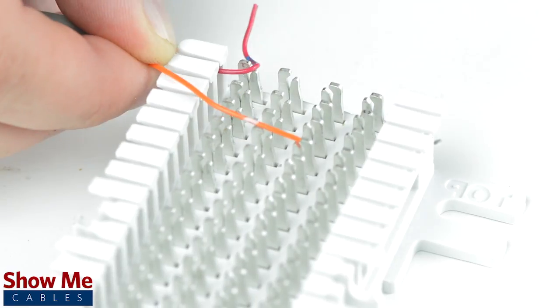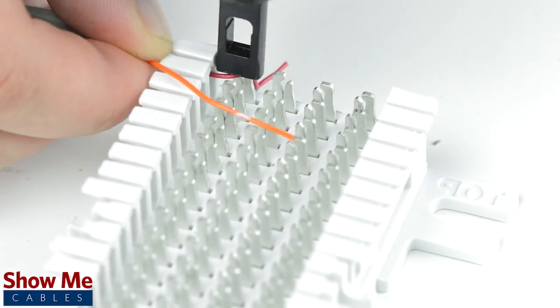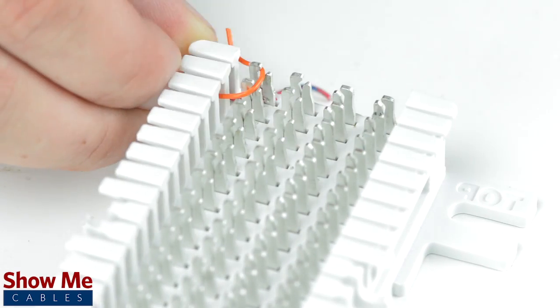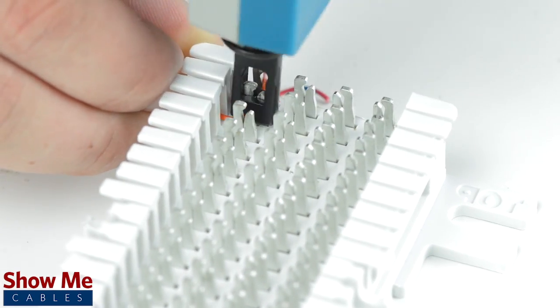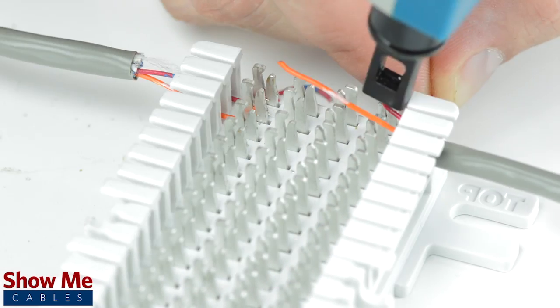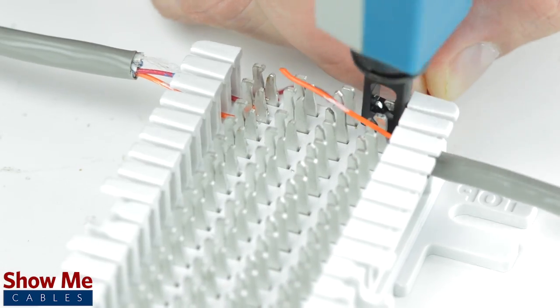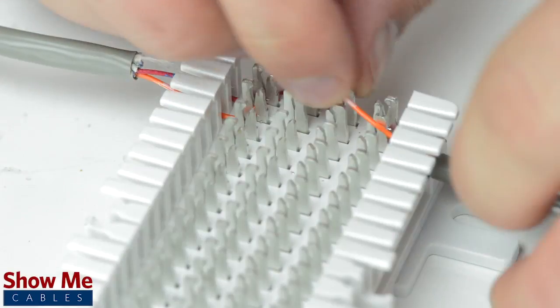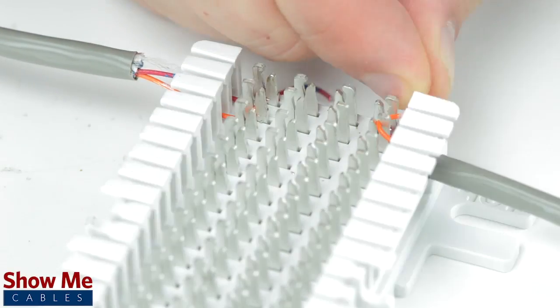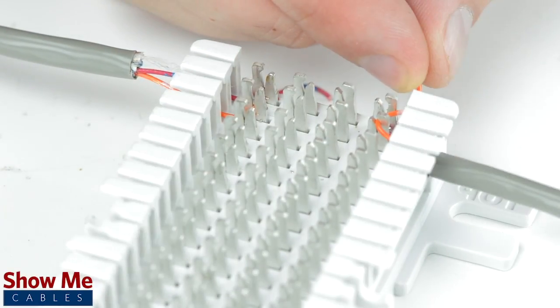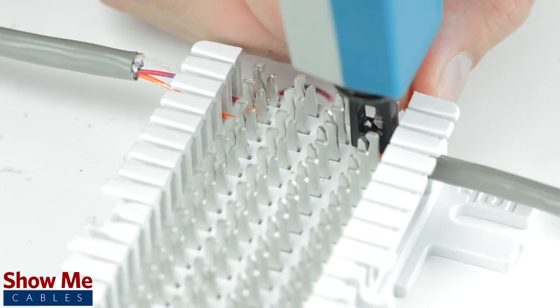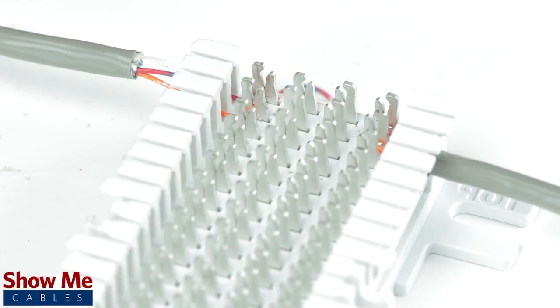For this example, we'll do a simple one-pair connection. You will take the incoming line and punch down into contact 1. You will then take your outgoing line and punch down into contact 4 in the same color code. Now both our incoming line and outgoing line are connected.